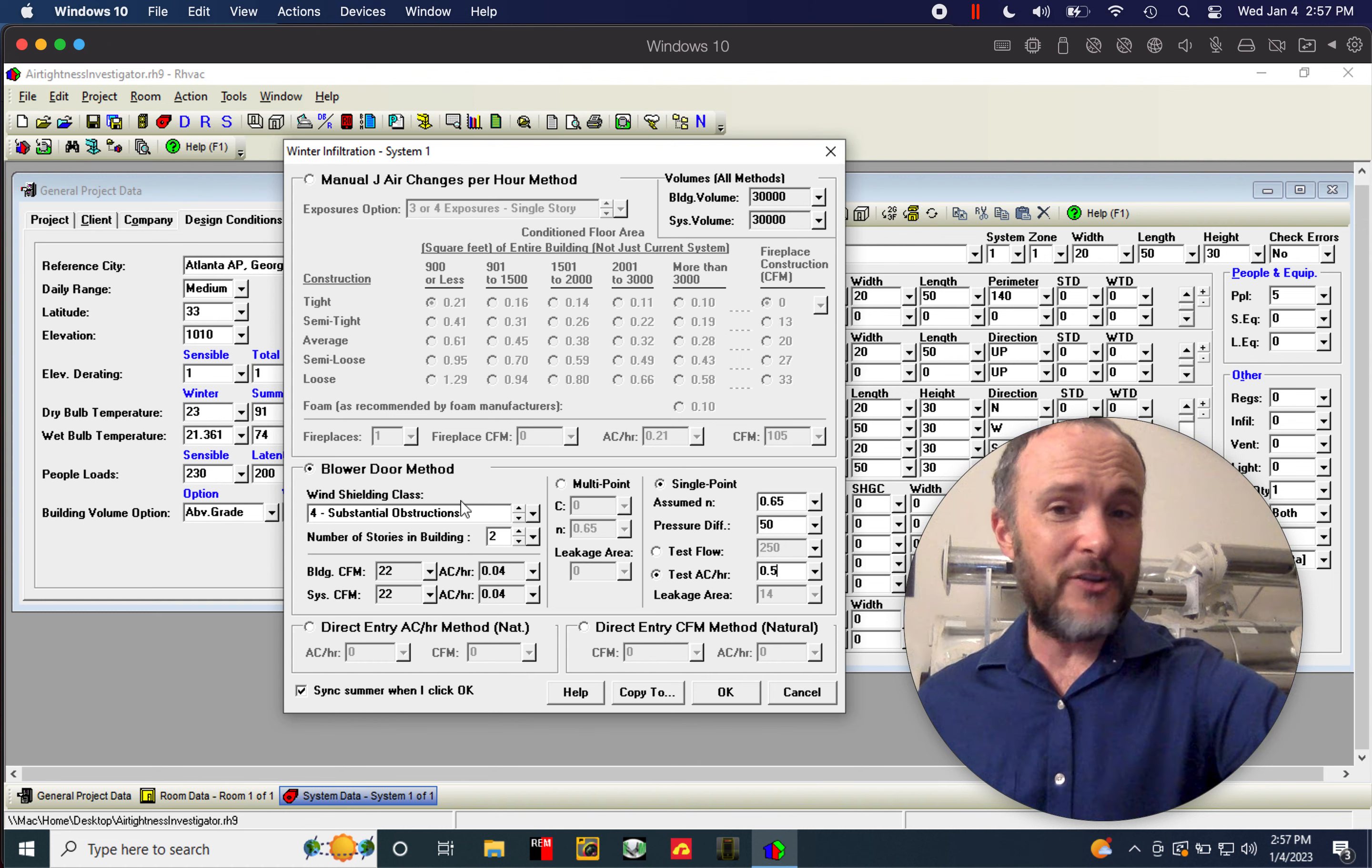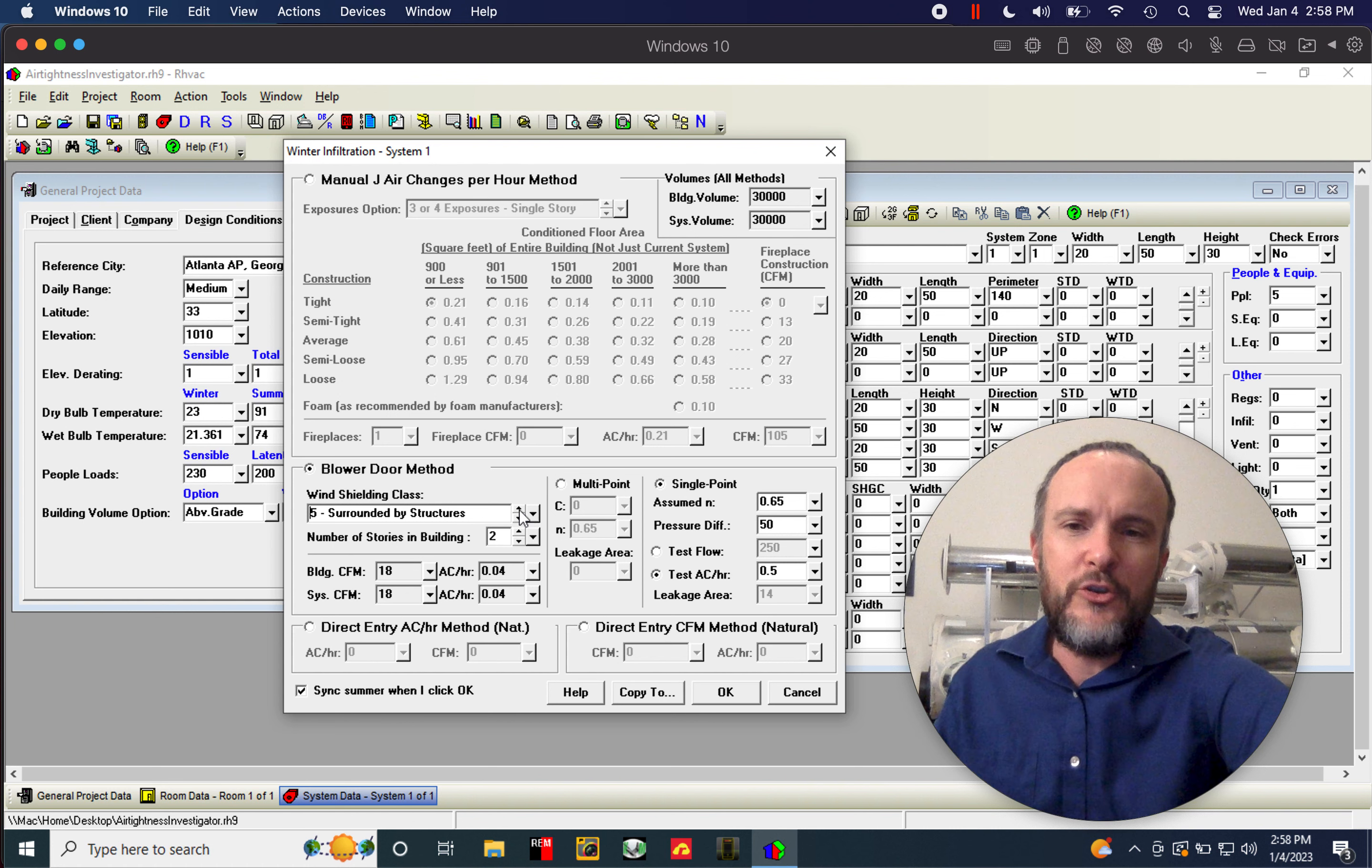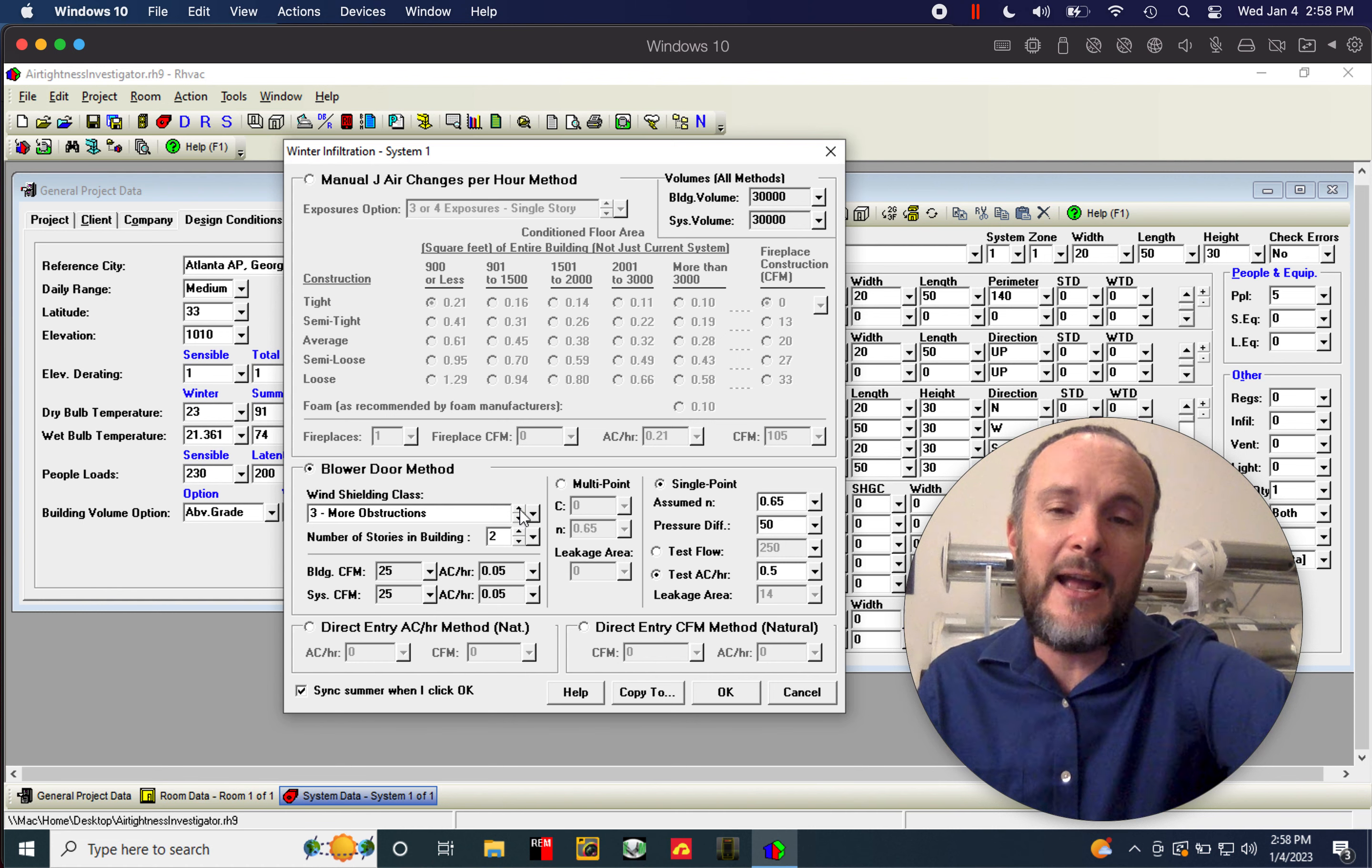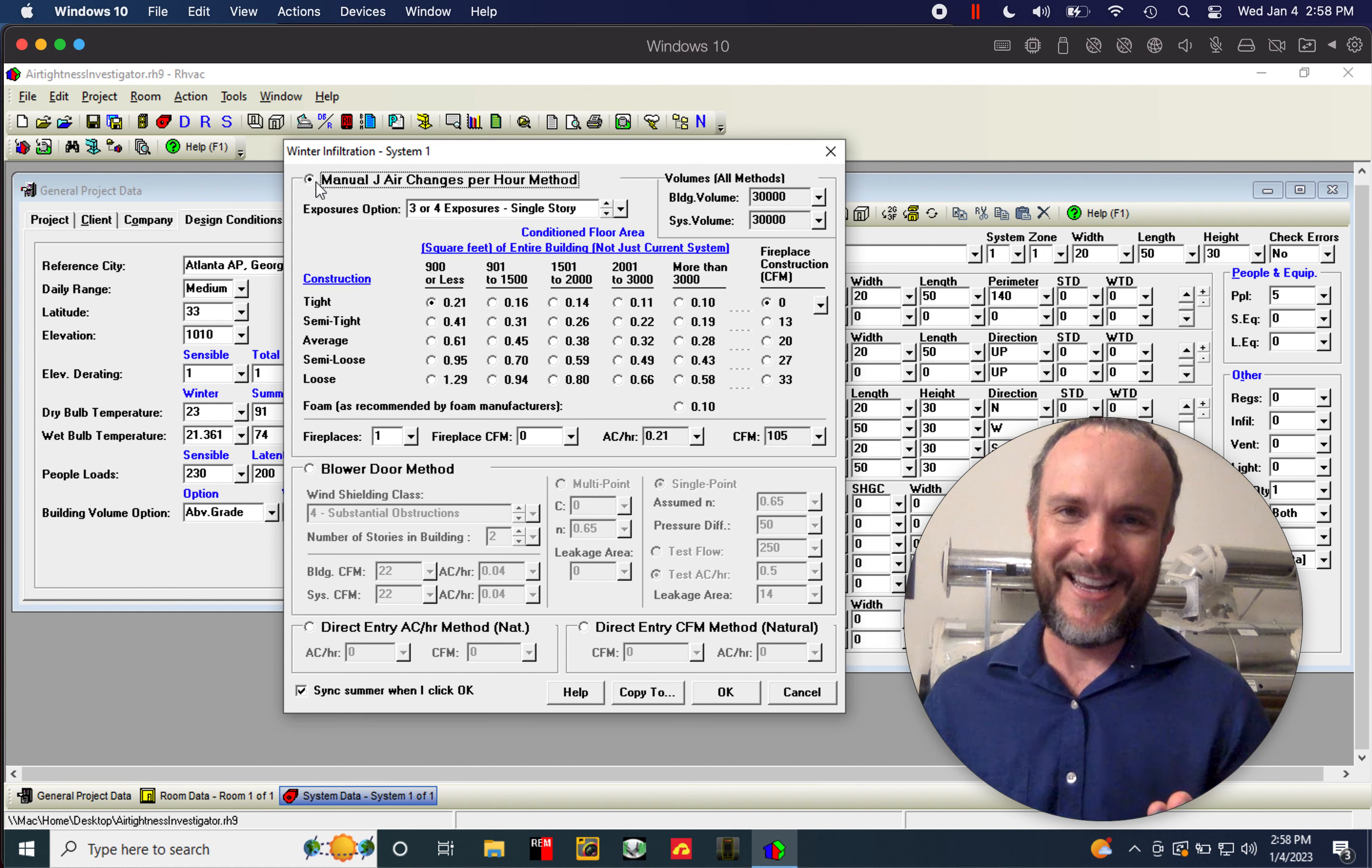Who knows what this means? Windshielding level five is completely surrounded by structures. That would be like a little home surrounded by other homes that are within like 10 feet. They might be taller. They might be as tall. They're not going to be shorter. Once you go down from here, substantial obstructions, more obstructions, few obstructions or no obstructions. That would be a house standing in the middle of the desert, totally exposed to the wind on all sides. So trees count. That would be few obstructions. A couple of houses nearby, a neighborhood. It defaults to substantial obstructions. And so you should generally leave it there if you're working in a neighborhood. But these are all things that actually change what's going on.